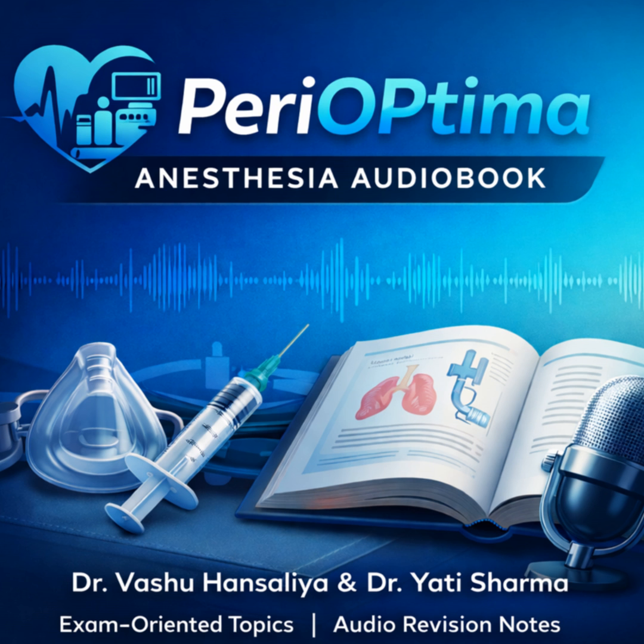Okay. Question 2. What is the ideal lockout interval? Answer: the ideal lockout interval is not a fixed number. It depends on the drug's circulation time and its time to peak effect. For IV morphine or fentanyl, 5 to 10 minutes is a standard starting point. Setting it shorter than the drug's onset time is dangerous as it encourages dose stacking.